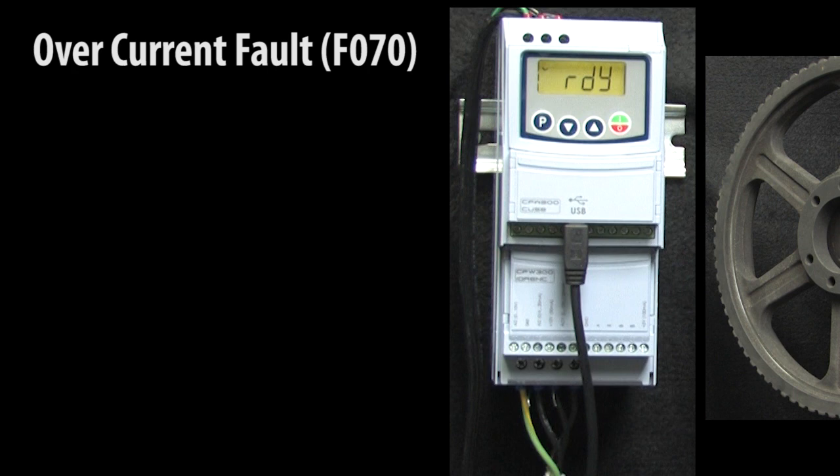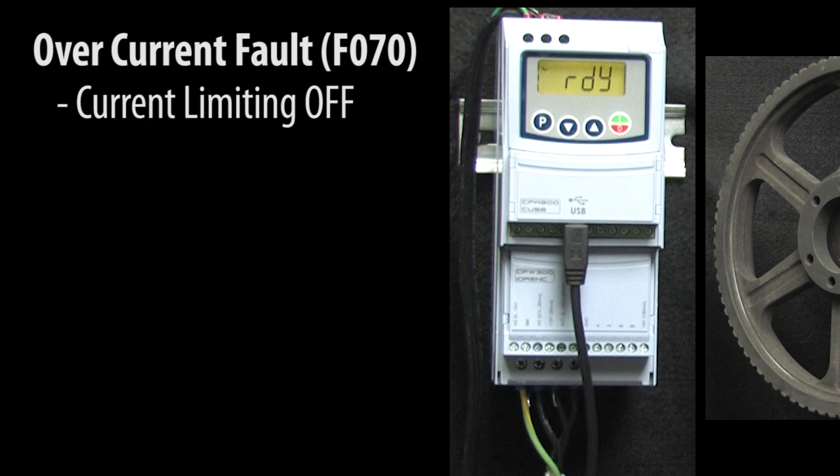Another possible reason for an overcurrent fault is that the built-in current limit function has been turned off. The WEG CFW300 drive has current limiting built in, so normally if you specify an acceleration ramp that is too short, the drive will automatically change the ramp time to prevent an overcurrent fault.